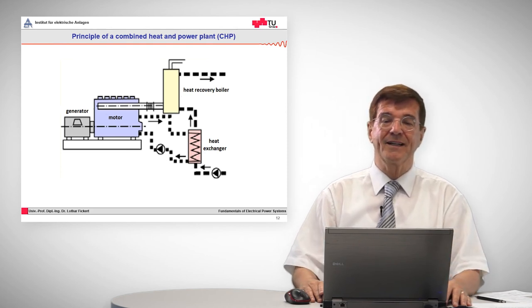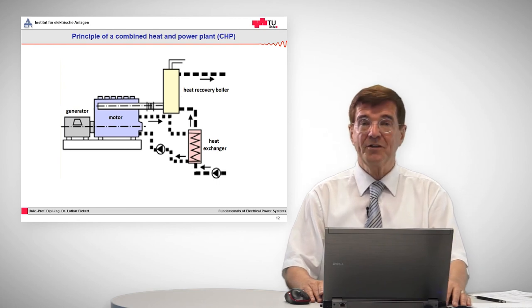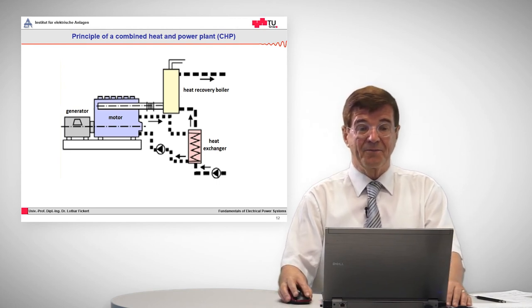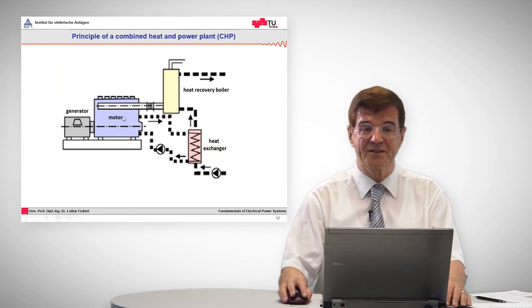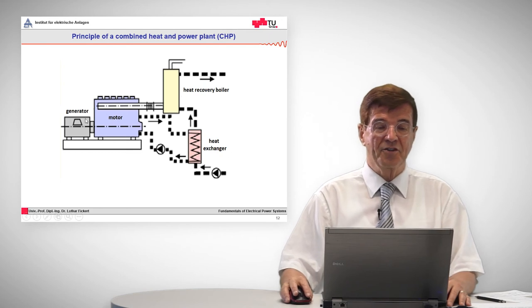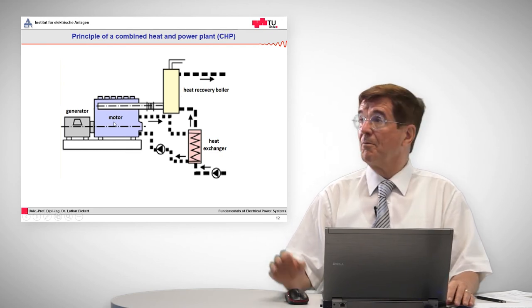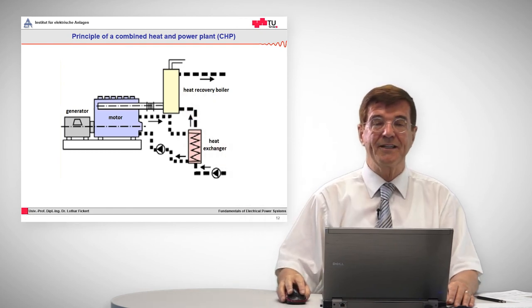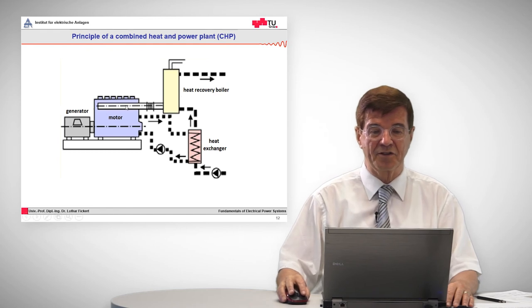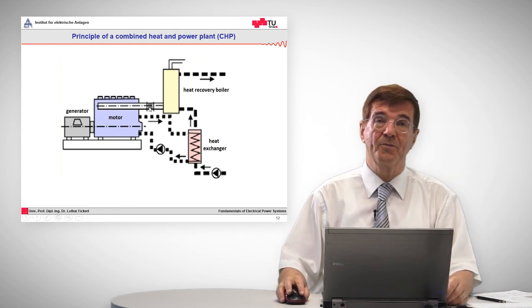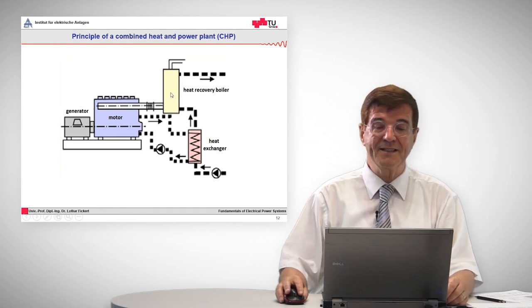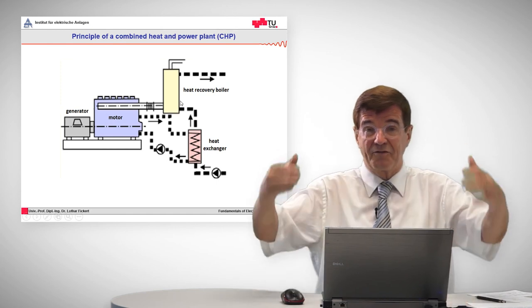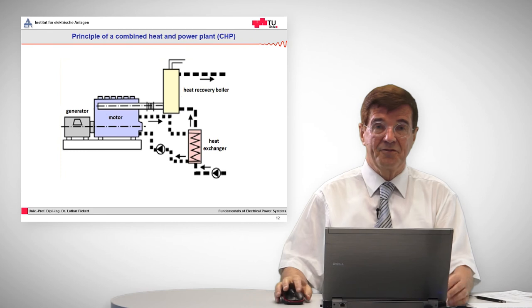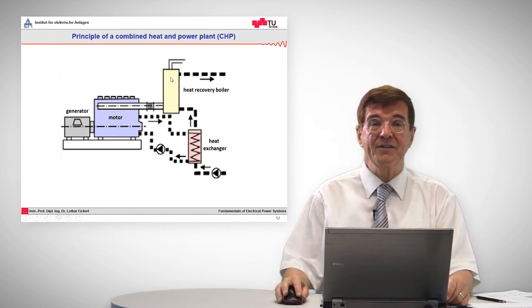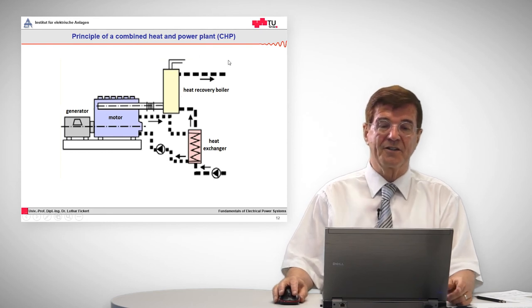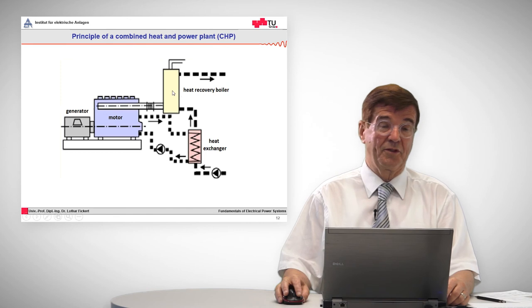The last way to transform chemical energy, for example from biogas or biomass, into electrical energy is done in the so-called combined heat and power plant, CHP. What happens here? For example, the combustion of the gases takes place in the motor, which is a more or less ordinary gas motor, which in turn turns the generator. And when we speak about the combined heat and power plant, we also combine heat output, because the exhaust fumes, when they leave the motor, are not let into the open air, but are put through a heat recovery boiler. You can think of it as a hollow vessel. In the vessel you have tubes, and the hot air goes around these tubes, and in the tubes you have water, which is used later for heating, for example, or other warm water processes.